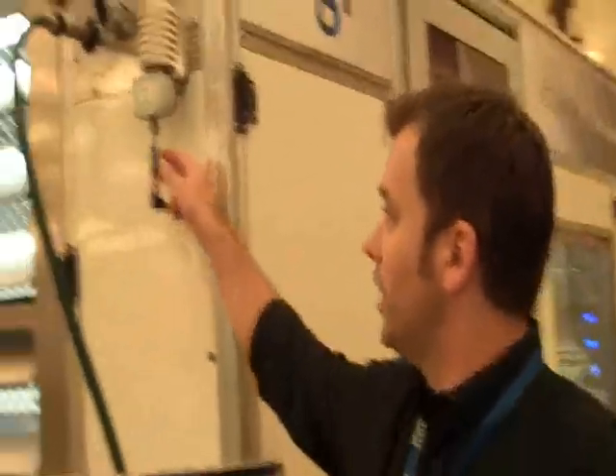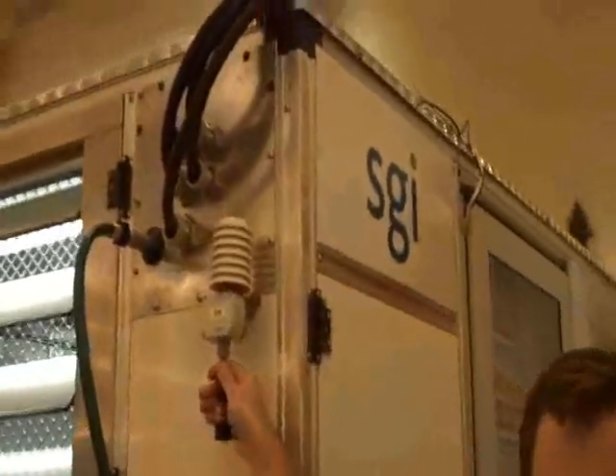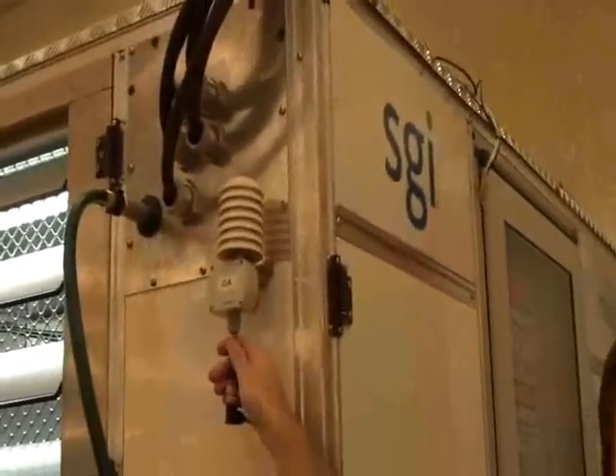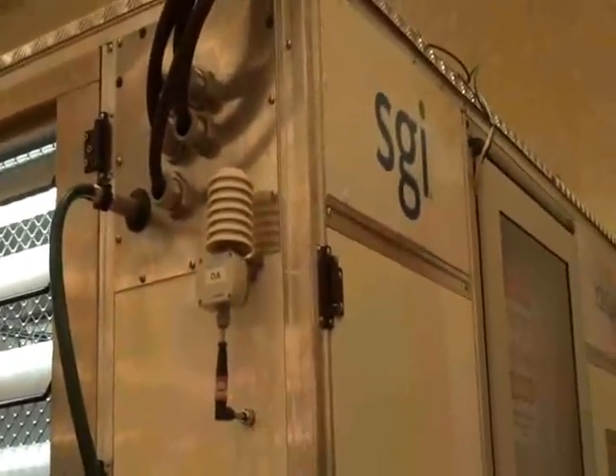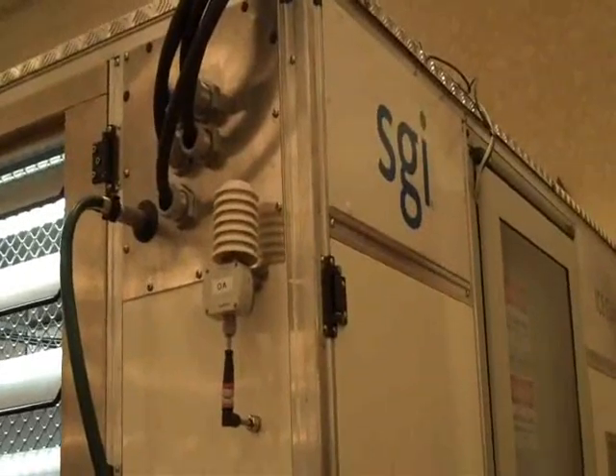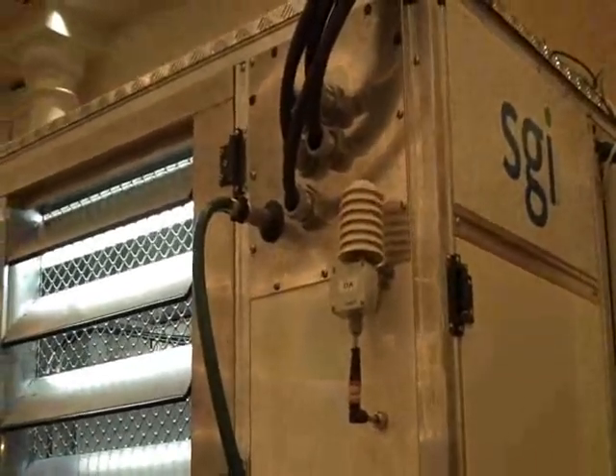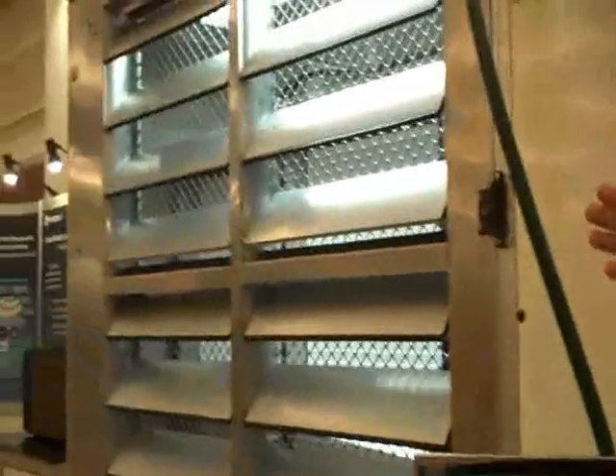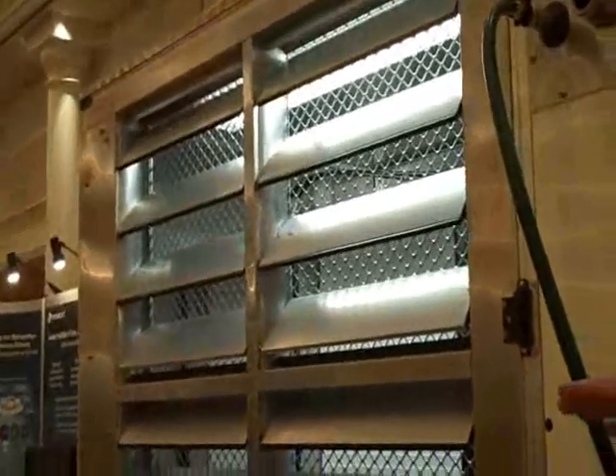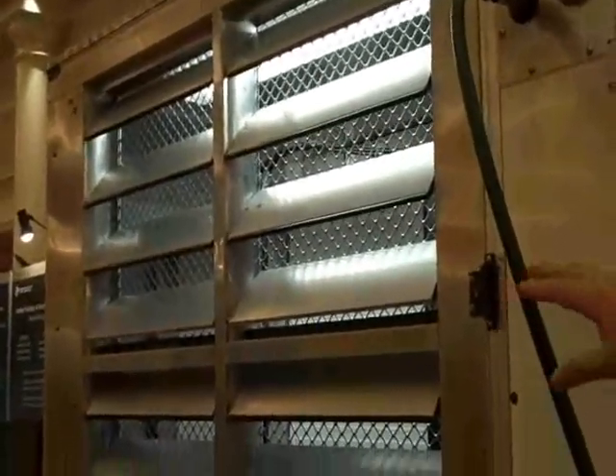Sounds great. Okay. So again, we'll start here with the outside air temperature and humidity sensor. It's very simple. What this does is let the monitoring control system, which we'll go into in great detail, know what kind of air, temperature and humidity is going on outside the unit. So you can see here we have the air inlet, where we have two separate levels of louvers, and the air enters the system this way.